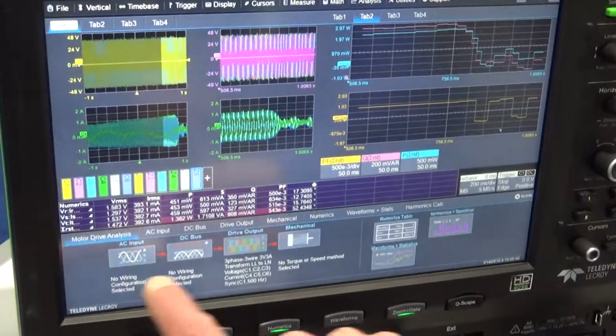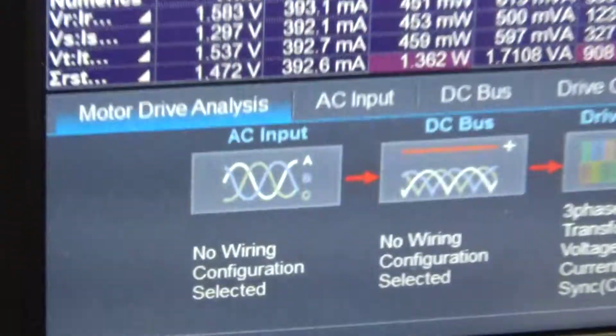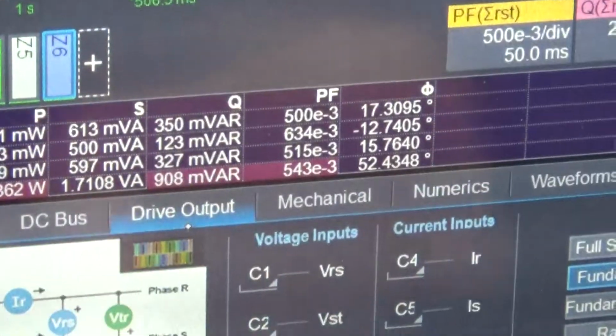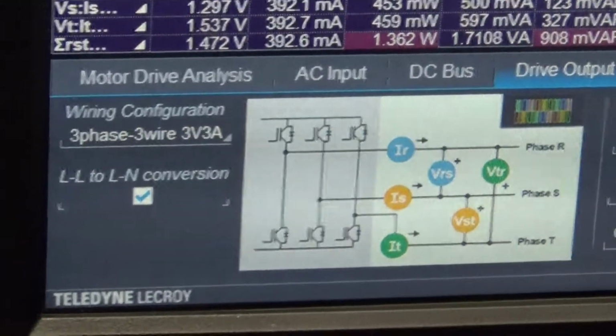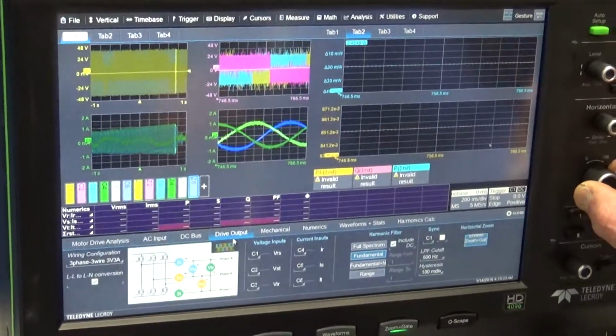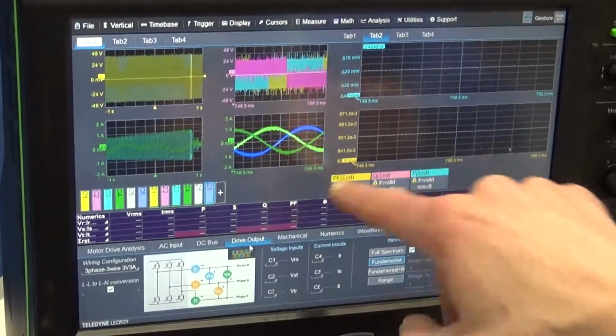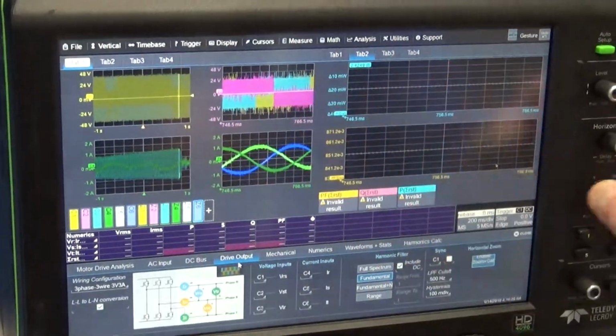This basically gives me the ability to look at the whole flow through a motor drive from the AC input to the mechanical output. Right now I'm just looking at the drive output, a 3-phase, 3-wire configuration. These are my 3 voltage and current signals right here. If I expand that out, I can see what looks to be PWM and my AC, my drive output current.